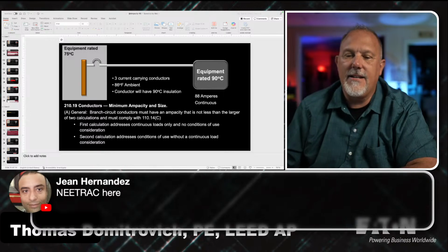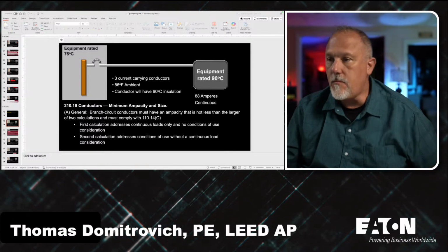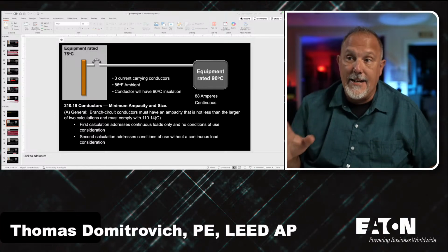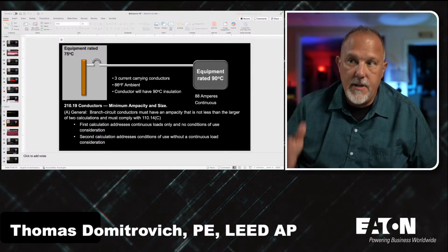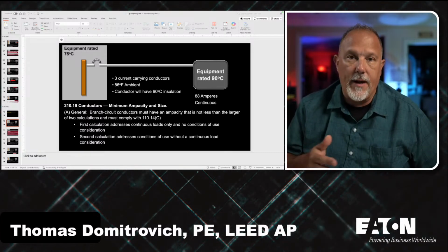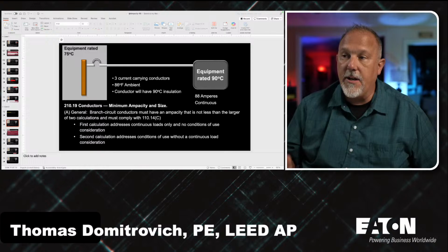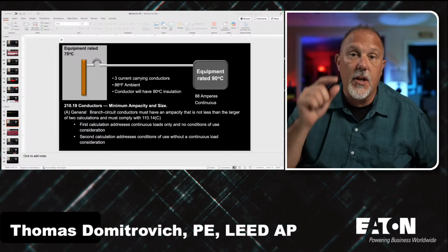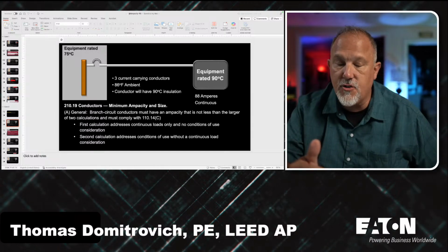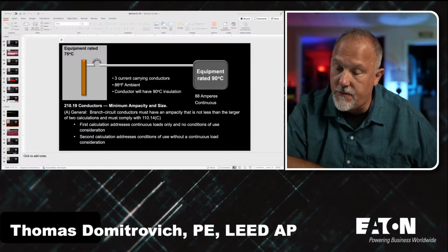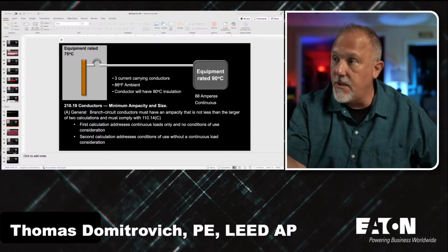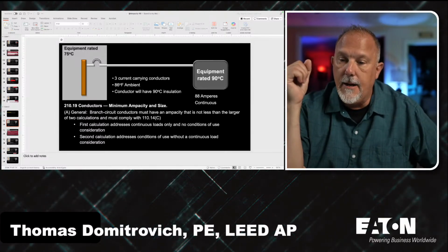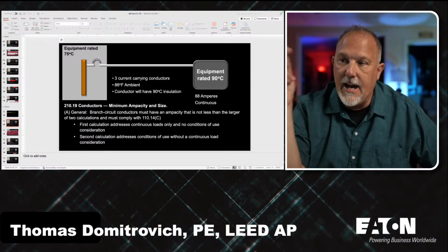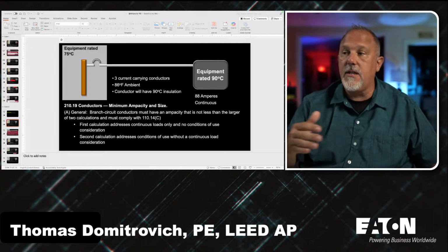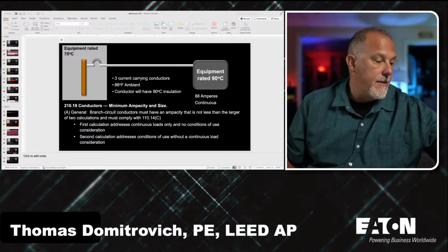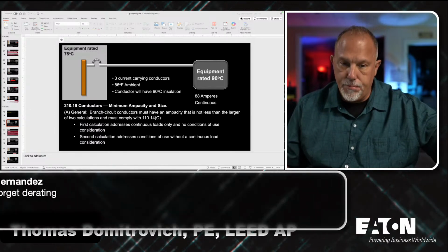Neetrac here, excellent. Okay, so we know that 210.19 governs the minimum ampacity and size for a branch circuit. It tells us that our branch circuit conductors have to have an ampacity that's not less than the larger of the two. First, I calculate to address continuous loads only. I don't do conditions of use. And the second, if I have continuous loads, in this case, it's all a continuous load. And then secondly, I have to address the conditions of use without the continuous load considerations.